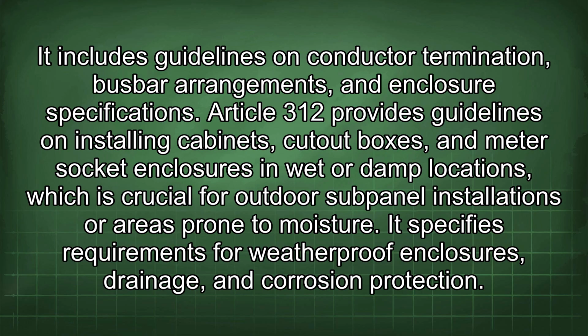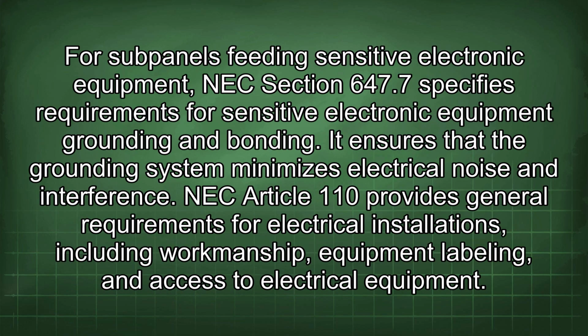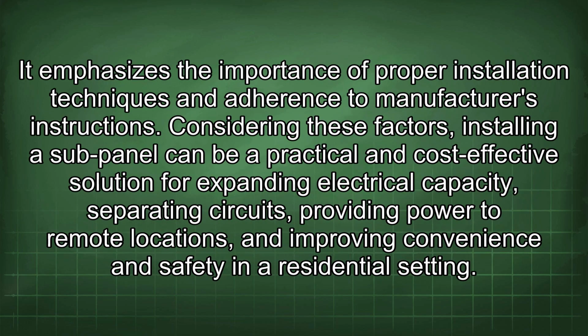It specifies requirements for weatherproof enclosures, drainage, and corrosion protection. For sub-panels feeding sensitive electronic equipment, NEC Section 647.7 specifies requirements for sensitive electronic equipment grounding and bonding. It ensures that the grounding system minimizes electrical noise and interference. NEC Article 110 provides general requirements for electrical installations, including workmanship, equipment labeling, and access to electrical equipment. It emphasizes the importance of proper installation techniques and adherence to manufacturer's instructions.